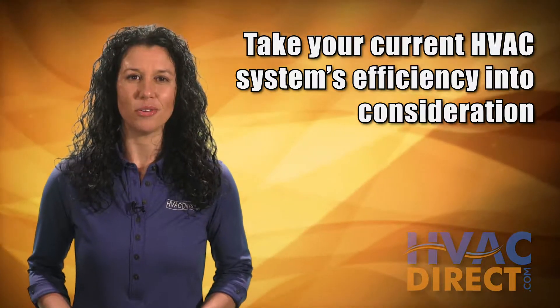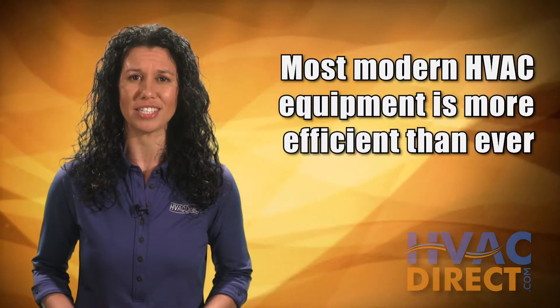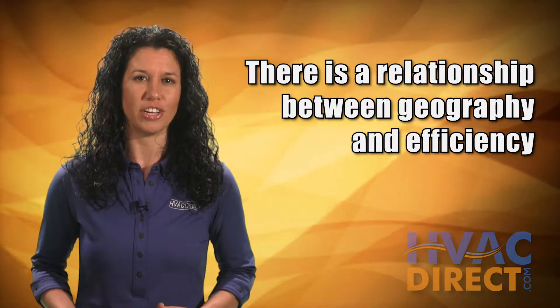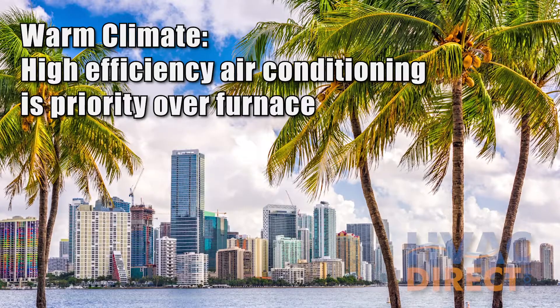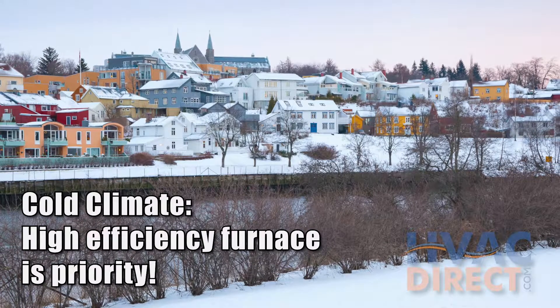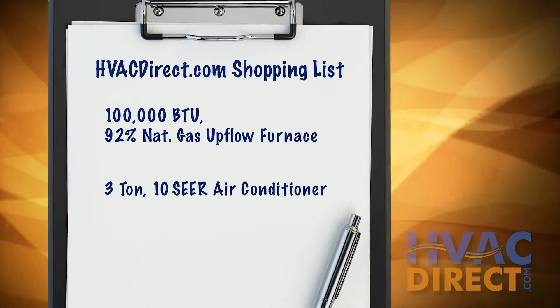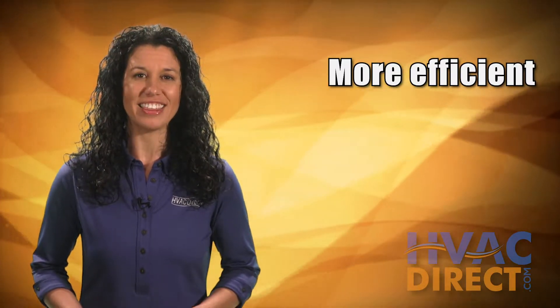This is also a good time to take your old unit's efficiency into consideration, especially if it was older than 15 years. Most modern furnaces and air conditioners will be more efficient than your old ones, but it is important to understand the relationship between geography and efficiency. For example, if you live in a warm climate and your electric bills are steadily on the rise, it's best to consider a high-efficiency air conditioner. On the other hand, if you live in the northern part of the country, you don't need a highly efficient air conditioner, but rather a more efficient furnace instead. In our example system, you will still look for the same size specs, but you might opt for a two-stage 97% efficient furnace with a variable speed blower and a 16-SEER air conditioner to gain the advantage of a more efficient system. The new system will perform better than the old one and be more efficient and less expensive to operate.